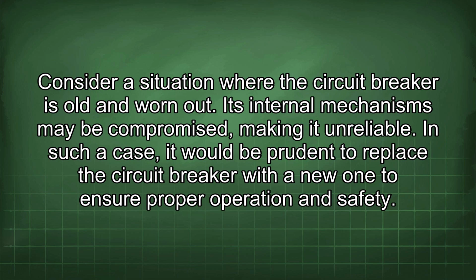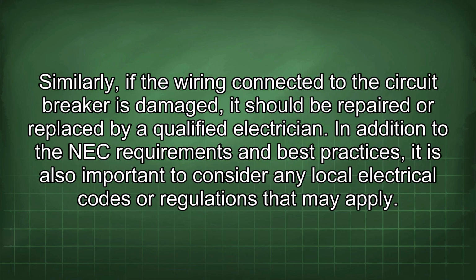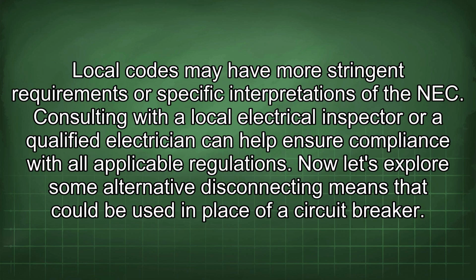Consider a situation where the circuit breaker is old and worn out. Its internal mechanisms may be compromised, making it unreliable. In such a case, it would be prudent to replace the circuit breaker with a new one to ensure proper operation and safety. Similarly, if the wiring connected to the circuit breaker is damaged, it should be repaired or replaced by a qualified electrician. In addition to the NEC requirements and best practices, it is also important to consider any local electrical codes or regulations that may apply. Local codes may have more stringent requirements or specific interpretations of the NEC. Consulting with a local electrical inspector or a qualified electrician can help ensure compliance with all applicable regulations.